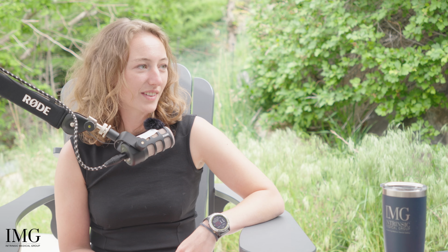And this actually relates right back to Dash 12 as well, in preparing for that biological endpoint testing and making sure that the sample really is representative of your final finished medical device, in terms of it having all of the constituent materials that would contact the tissues. It's representative of the manufacturing and the finishing processes, as well as any sterilization that might have been performed on it. And honestly, that's the hardest part of these studies half the time, being able to create the samples to implant that replicate the normal product.